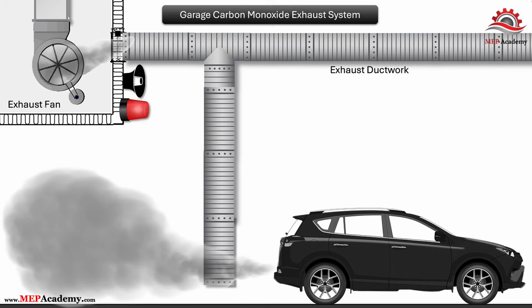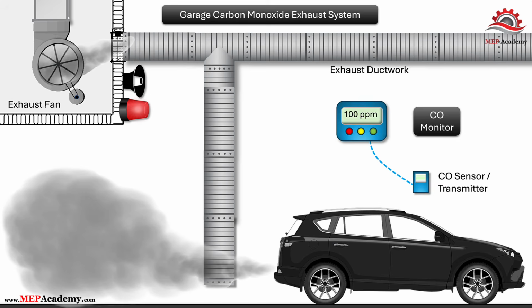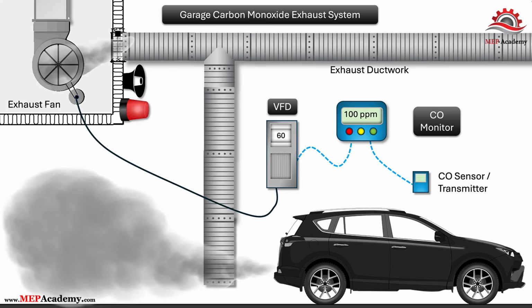Next, we have a garage exhaust system. Instead of operating the garage exhaust fan at full speed continuously, install a carbon monoxide, CO, monitoring and control system with multiple CO sensors throughout the garage. These sensors are connected to a variable frequency drive, VFD, which modulates the exhaust fan speed to maintain carbon monoxide concentrations within safe limits. When vehicle activity is low and carbon monoxide levels are minimal, the VFD reduces fan speed, significantly lowering energy consumption. As vehicle traffic increases and CO levels rise due to combustion engine operation, the controller automatically increases fan speed to provide the required ventilation and maintain code-compliant indoor air quality.